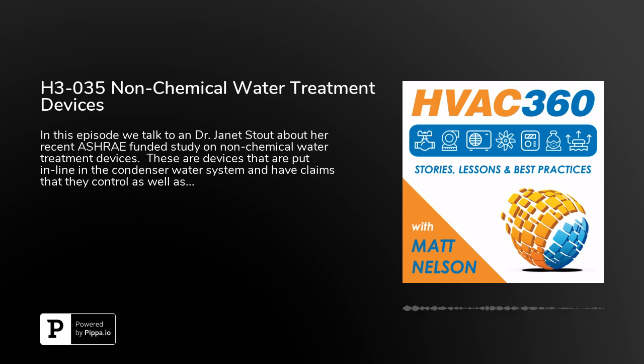And the takeaway was that when we did the statistical analysis of the difference between the recovery of bacteria from the tower with the test device and the tower that was the control, there was no significant difference. And what that means is that we were unable to demonstrate that any of these five devices were capable of controlling the microbial fouling in the cooling tower.